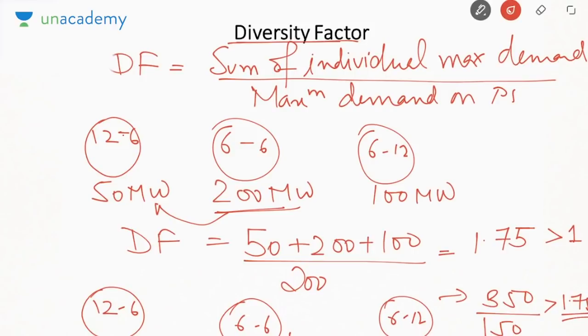So diversity factor should be as high as possible so that loads are distributed throughout the day and the maximum demand at a time on the power system is reduced, because now the installed capacity of the power system should be greater than 150. Earlier it should have been greater than 200 because installed capacity must always be greater than the maximum demand. So by making the loads more diverse or more distributed throughout the day, we have reduced the maximum demand on the system, and that is how we have reduced the installed capacity and the cost of the system. So diversity factor should be high.